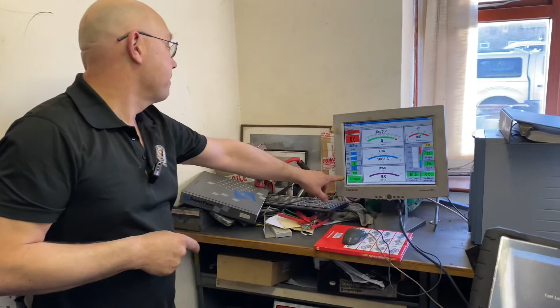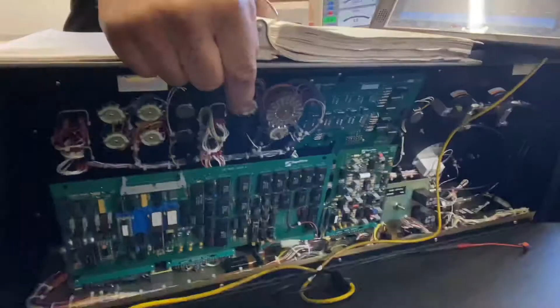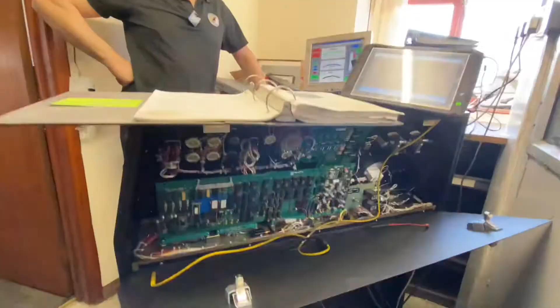So once you fit the load cell, we then need to hang weights on the dyno, take voltage readings, and with a tiny little screwdriver, go in the back of the console and adjust various voltages to get the correct readings. Then we go in the cell and hang weights on calibration arms, which I'm going to show you in a second, which turned out to be more complicated than originally expected. And hey presto, we're away.